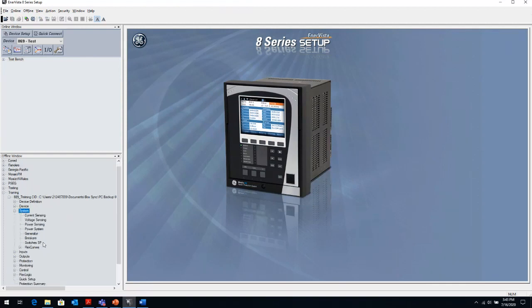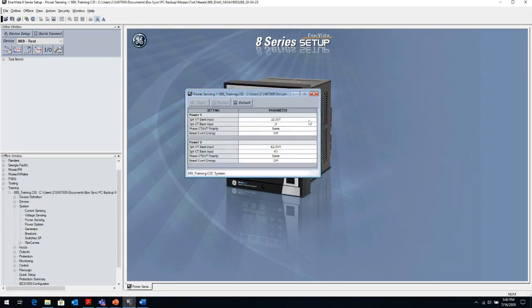The only other thing I wanted to mention is, when we look at the power sensing and set up the power, you'll know there's a setting that says CT and VT polarity. Remember I talked about that differential? Depending on how you set up that differential connection, whether it's just a generator zone or whether it's a transformer in the differential zone, the connections might vary a little bit. So you might have to come in here, and if I want to meter correctly, meaning I want to see power leaving the generator or going into my system, then I may need to reverse the connections here so that my forward metering is correct.